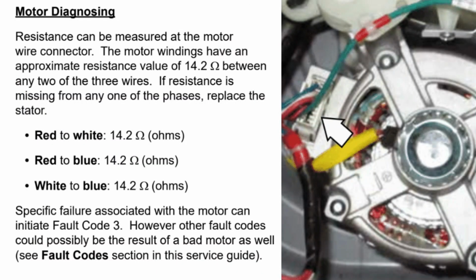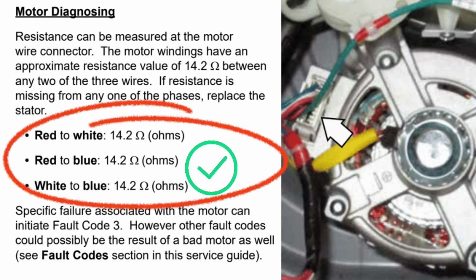To check the motor windings, it's best to test directly at the stator, which is the motor itself. All three windings should read approximately 14.2 ohms, and they should be evenly balanced. If one winding reads significantly higher, for example 30,000 ohms, that indicates excessive resistance and a defective motor. If your readings are 14.1 or 14.3, but all three are consistent, that's fine. They just need to match closely.